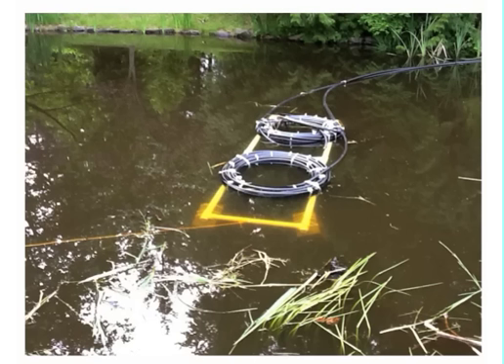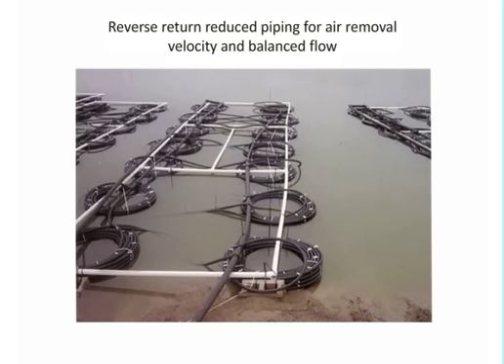Also bear in mind, you're going to need to add some weight to your supply and return pipes going to and from the beach. You want to make sure you're doing that so your weight doesn't cause any abrasion, rupture, or breach in that pipe. I oftentimes would use a flexible PVC pipe as a sleeve over some of those areas where I would apply my weighting or anchoring to the lake bed.